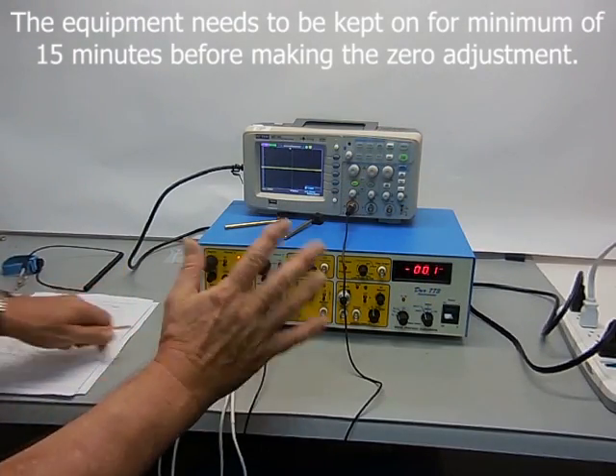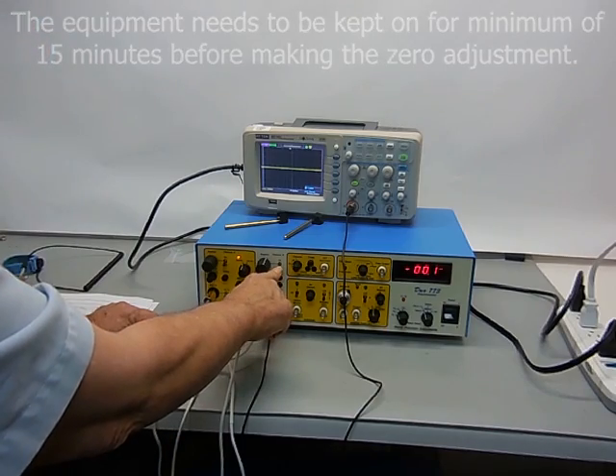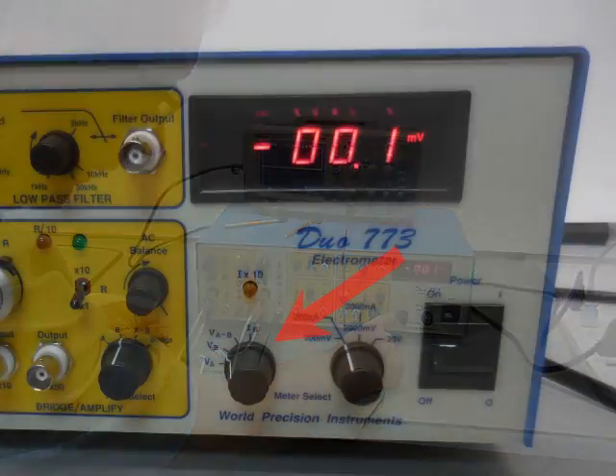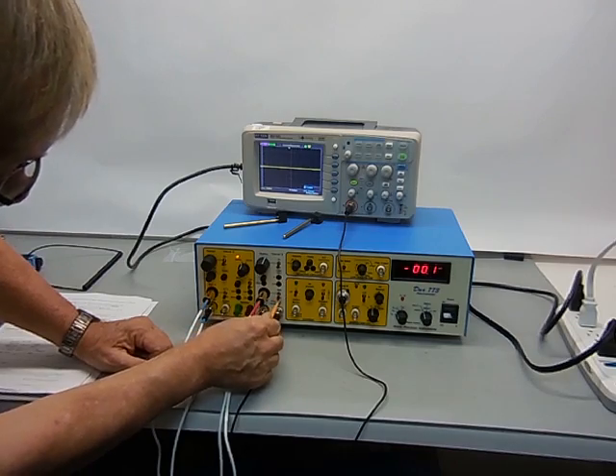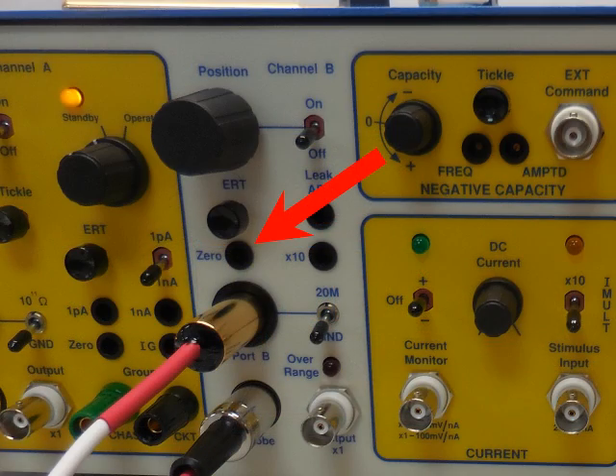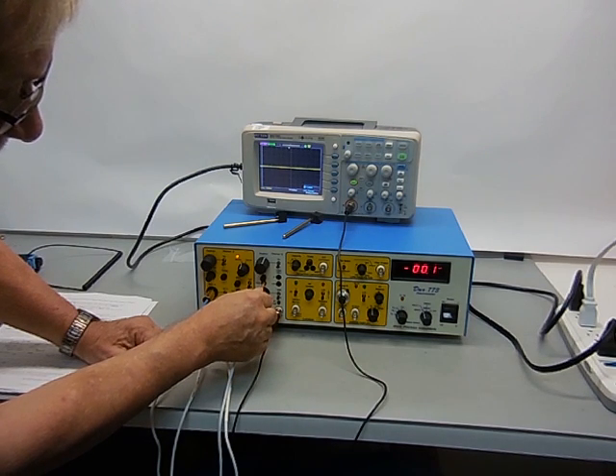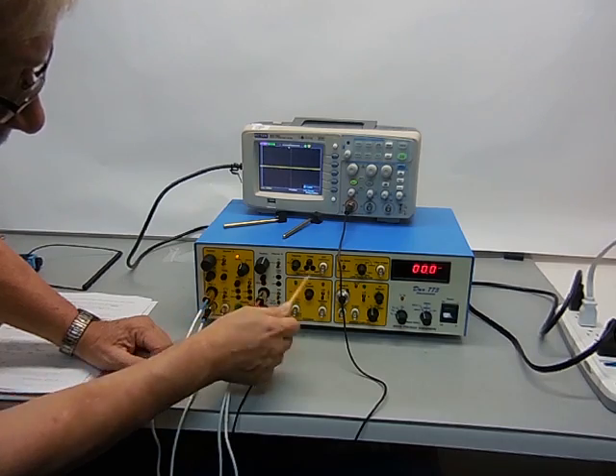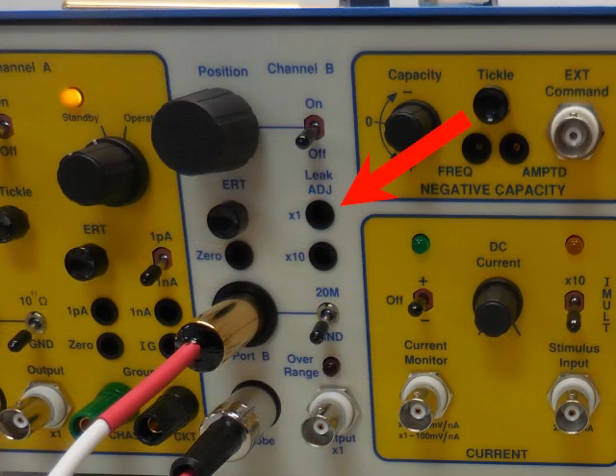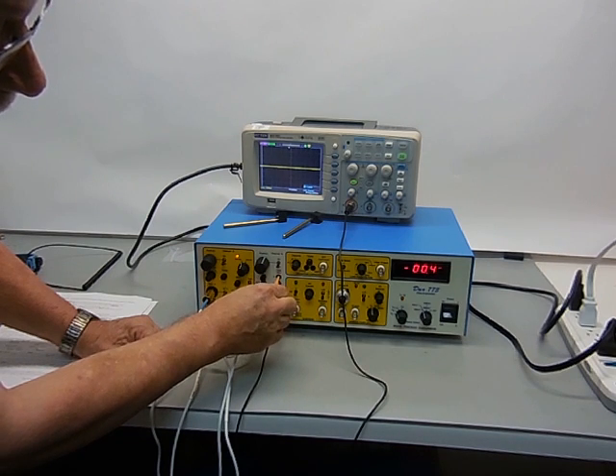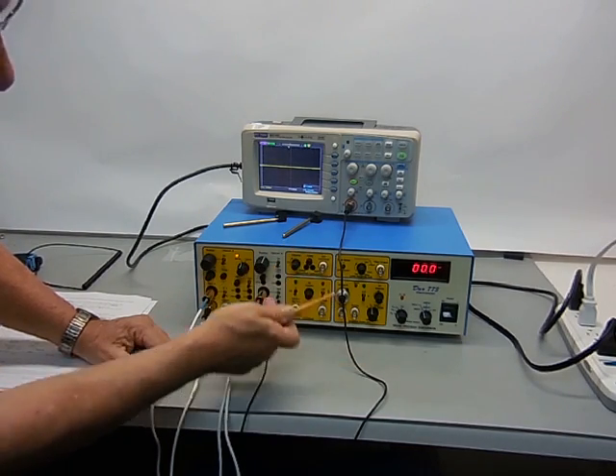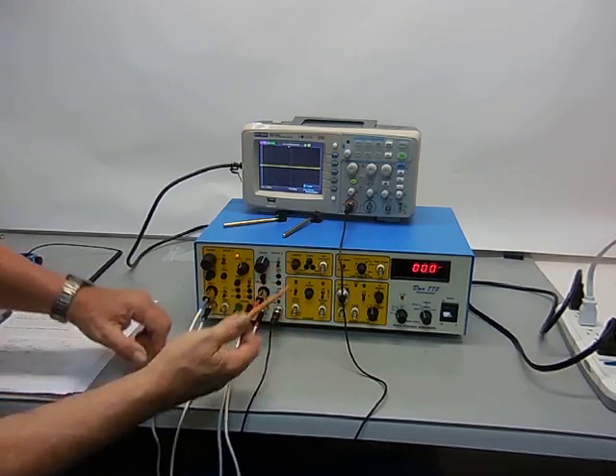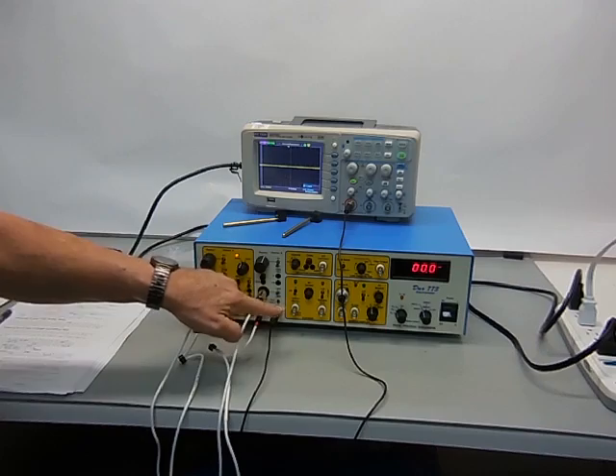To adjust the channel B probe, first make sure the position control is off. Center capacity, we're in VB mode, 200 millivolt mode. Notice I have negative 0.1 millivolt. In the ground position, we have to set the zero point on the probe by putting the adjustment tool in here and adjusting until this reads zero. Step two is adjusting the leakage, the 1X leakage. We turn the 20 megaohm switch on and adjust how much leakage we've got to zero. This probe is now properly adjusted. When you're at ground potential you're at zero, and at 20 megaohms we're at zero.